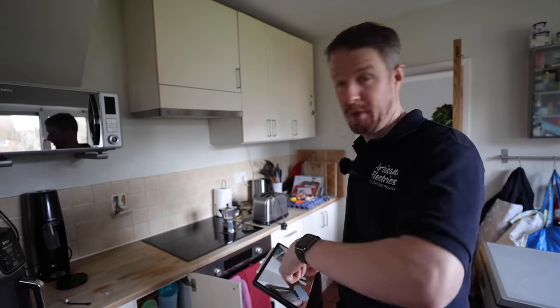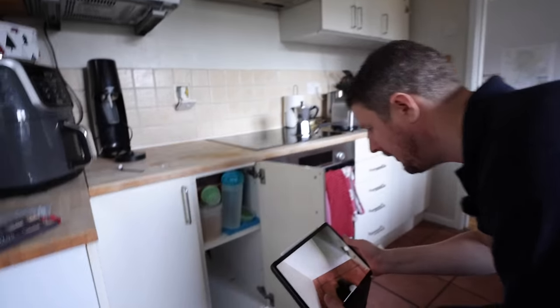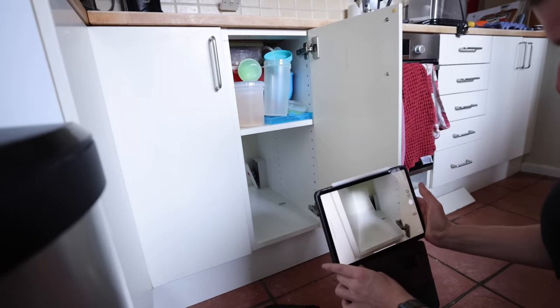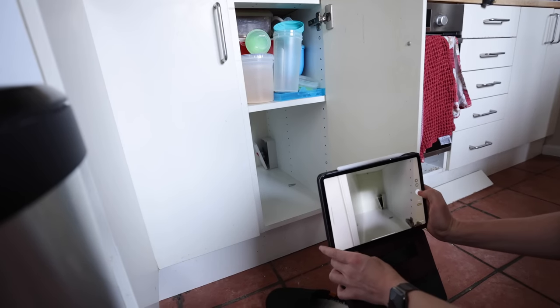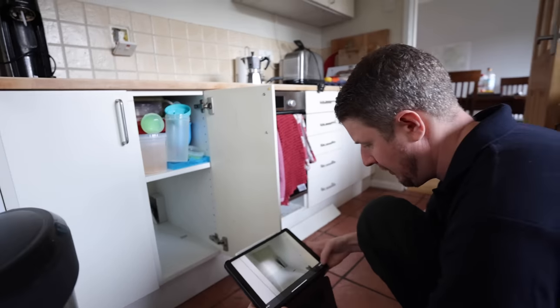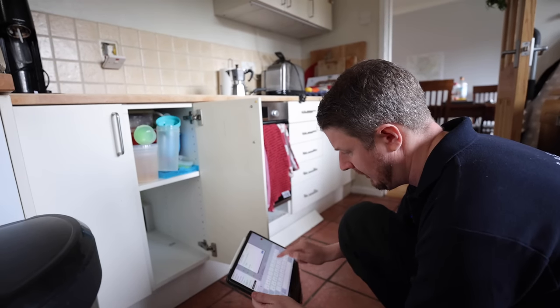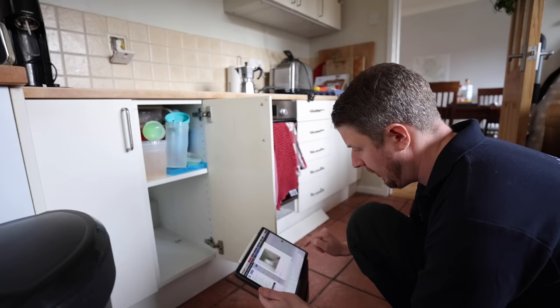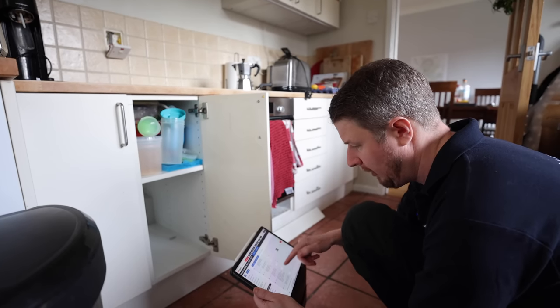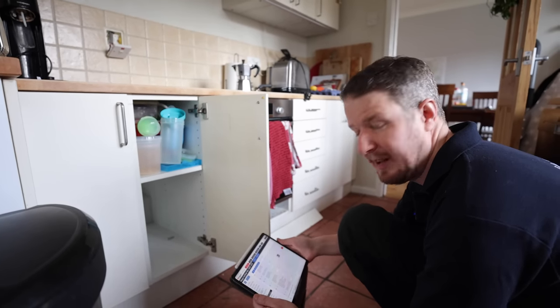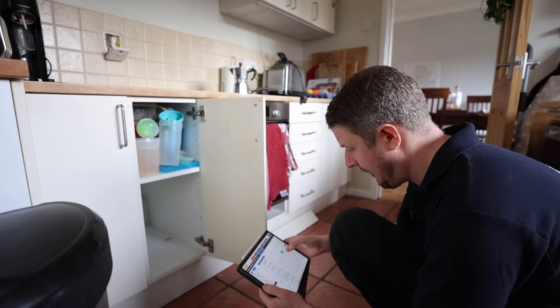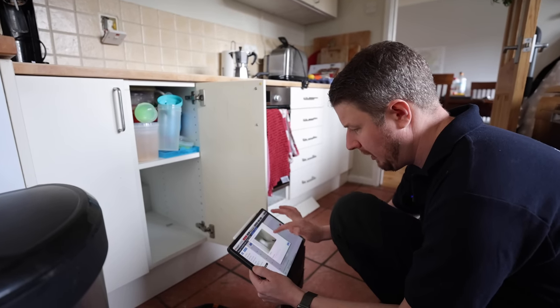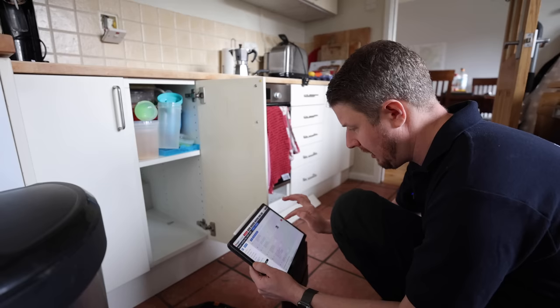We can even add a brief description of the photo, and that just adds it to our schedule of inspections. So one of the things I'm observing on this report is really difficult to access certain items of electrical equipment. For example, down here, if I show you, this is the switch for the hob, and it's right in the back corner of the cupboard. So I'm just going to take a picture of that and then add that in to the report.